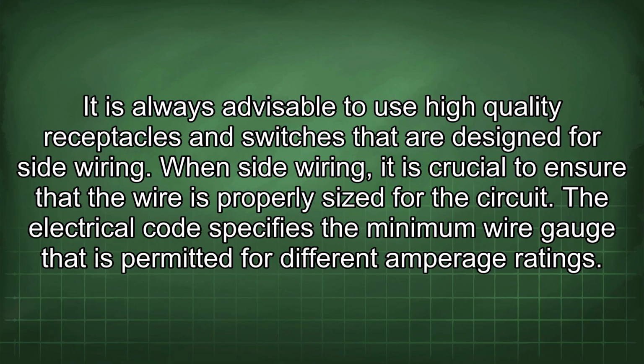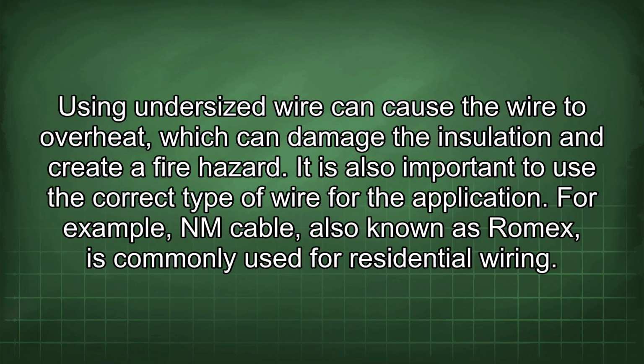When side wiring, it is crucial to ensure that the wire is properly sized for the circuit. The electrical code specifies the minimum wire gauge that is permitted for different amperage ratings. Using undersized wire can cause the wire to overheat, which can damage the insulation and create a fire hazard.